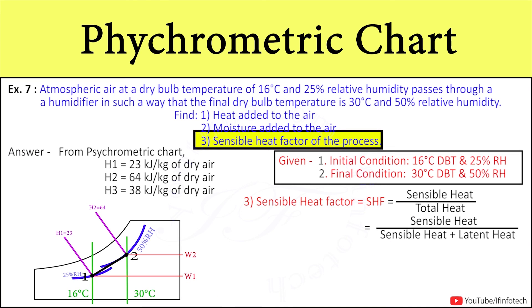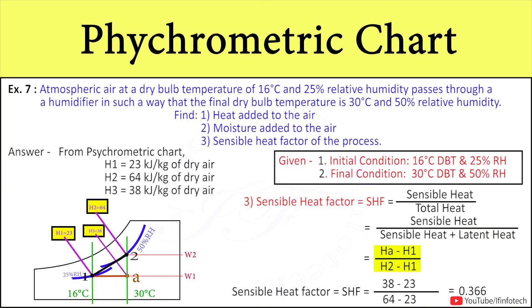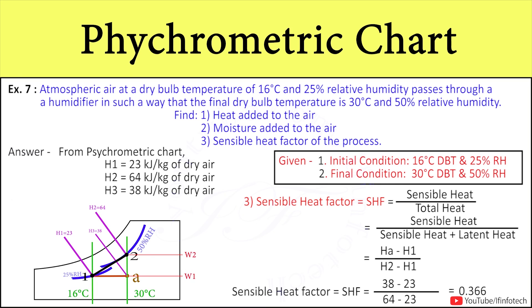To find the sensible heat factor: SHF is the ratio of sensible heat to total heat, where total heat equals sensible heat plus latent heat. The enthalpy difference from point 1 to point A is the sensible heat, and from point 2 to point A is the latent heat. Using h1, h2, and h3 in the formula, we get the sensible heat factor as 0.366. Thank you for watching this video; stay tuned with IF Infotech and subscribe to our channel.